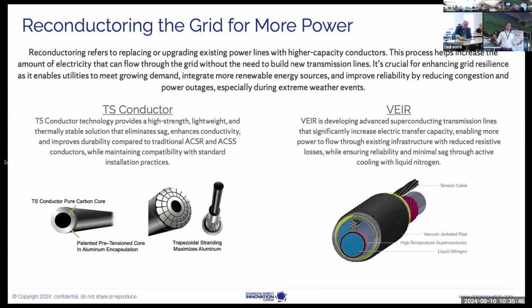Our peak demand in Virginia is in the summertime, our winter and summer peaks aren't equivalent, we have a higher peak in summer. So if we can reduce that sag... because as steel and aluminum heat up, they want to expand, and so the line sags on your towers. You can only allow so much sag before you have to downrate that line. So when the line is downrated at the peak time you need power, when everyone's plugged in their car, turned on their AC, and is cooking dinner at night, when it's hottest during summer months, you have to downrate your transmission lines because they'll sag too much, they'll arc, they'll drop, and you're going to have some big problems. TS Conductor came up with a way of solving all of those problems.